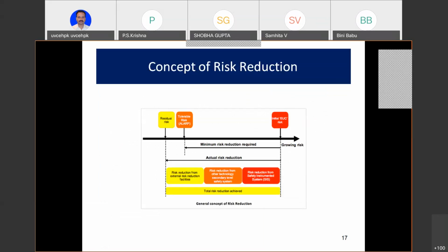Now, this is your general concept of risk reduction. You're starting with the initial equipment under control risk, like that plant which we saw. First, that hypothetical plant. Then the first is risk reduction from the safety instrumented system, which has brought the risk needle up to this point. And then they say risk reduction from other technologies, secondary level safety systems, etc., that we may be using some other methods also, even mechanical, maybe put two relief valves, we don't know all that.